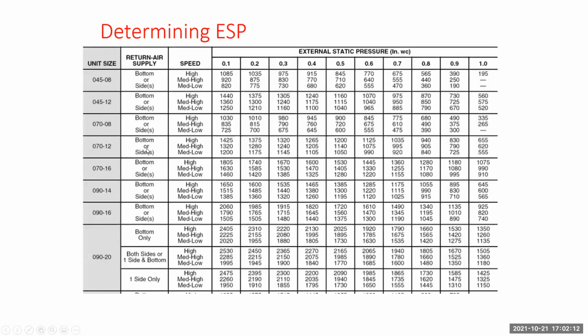Here's your airflow chart. I'm going to show you, say we're on a 70-08 system. Our static was 0.6. We're running on high. We're running 845 CFM. We're 350 to 400 CFM per ton. Keep that in mind. If you do not have an airflow chart for a system when you get there, aka the instruction manual is not there, call us. We can send you something.